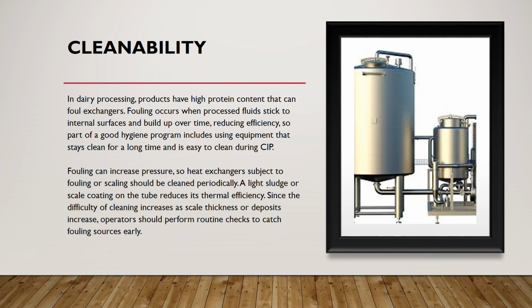Fouling can increase pressure, so heat exchangers subject to fouling or scaling should be cleaned periodically. A light sludge or scale coating on the tube reduces its thermal efficiency. Since the difficulty of cleaning increases as scale thickness or deposits increase, operators should perform routine checks to catch fouling sources early.